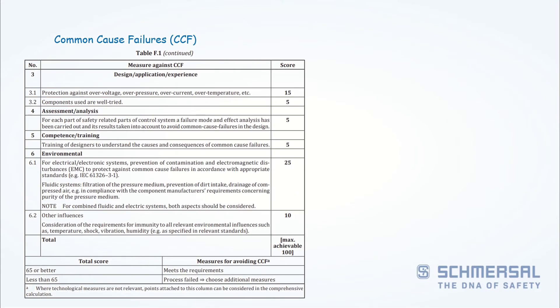It also looks at common cause failures, where the standard says let's look at your two-channel system. It will give you procedures — each procedure is given a score — and you have to select and implement enough procedures to get a score of 65 or more. Then you can claim that your safety function is resistant against a common cause failure.